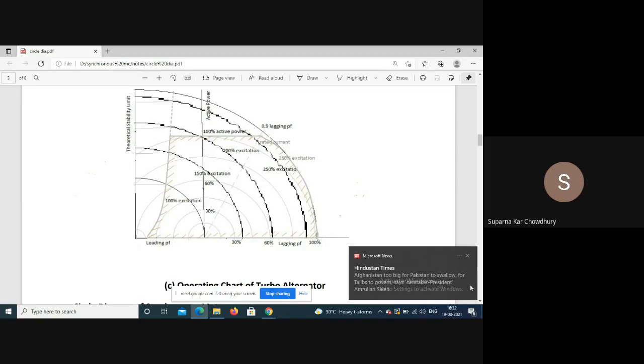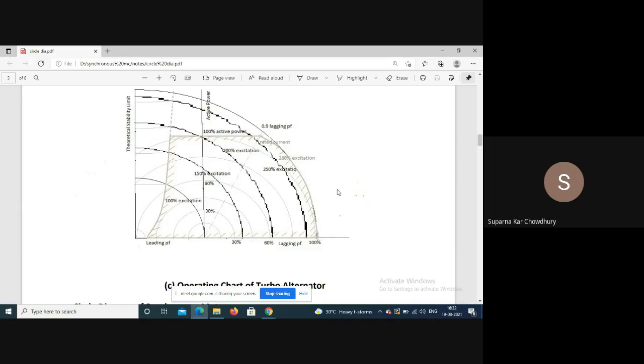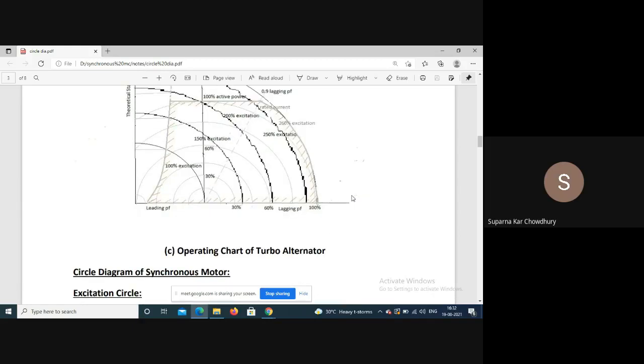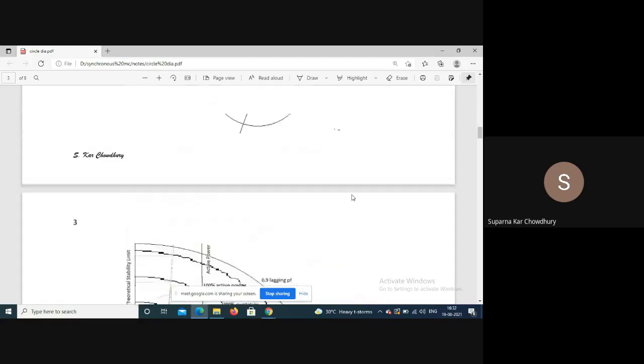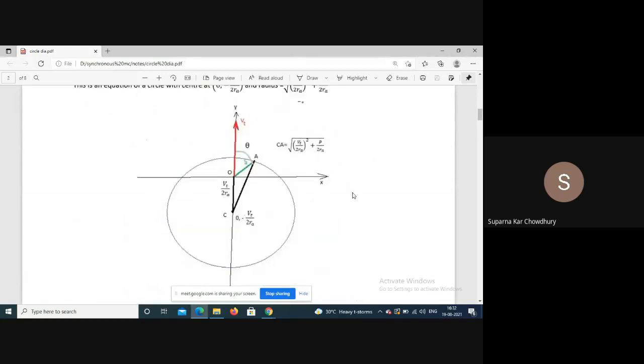The safe operating area is the shaded region defined by the current rating circle, the excitation circle, the active power line, and the 10% stability margin line. When the machine operates within this area, it will not exceed any of its ratings.